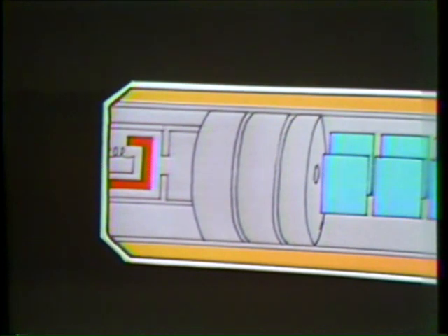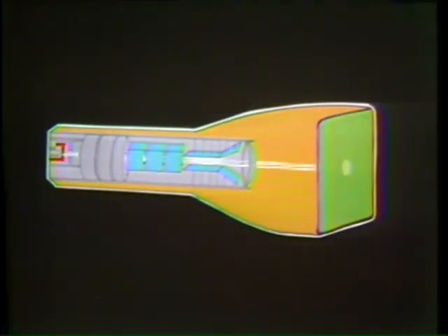At the far end of the electron gun is the cathode grid assembly. The cathode is like a pan of water on a stove. Electricity heats up the cathode and causes it to give off electrons, just like a pan of water heated to boiling gives off steam. The electron gun focuses and accelerates the electrons given off by the hot cathode into a narrow beam. This beam strikes the phosphor screen that glows brightly at the point where the electrons strike.